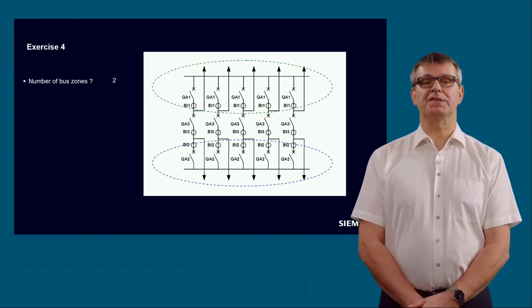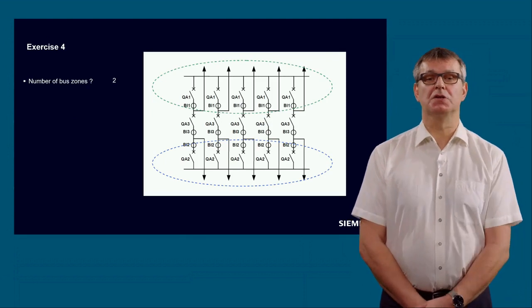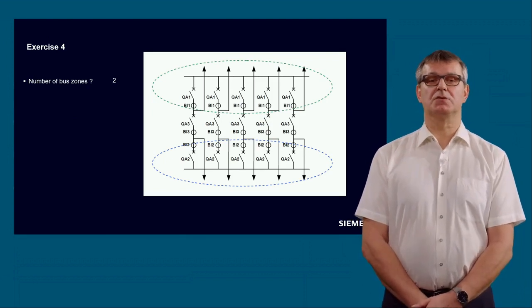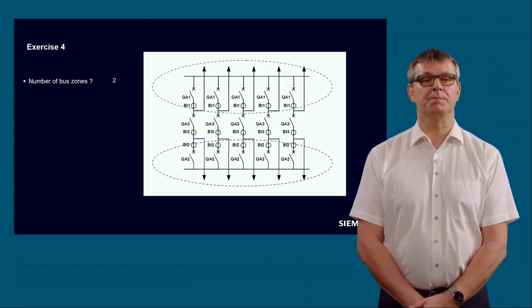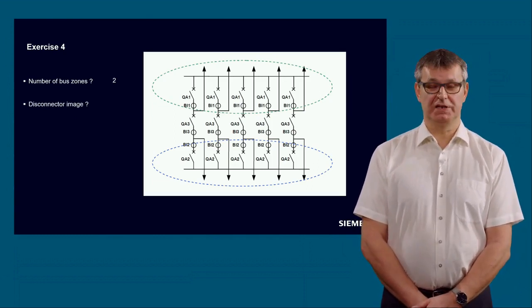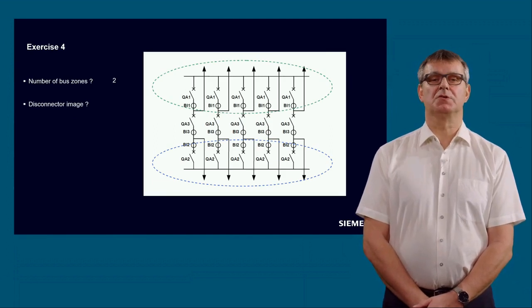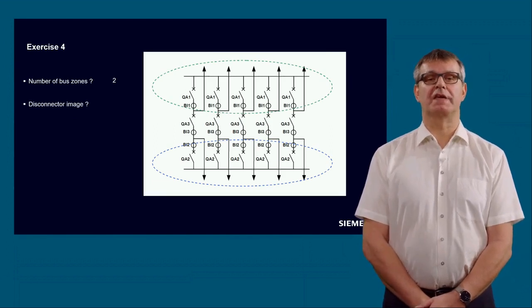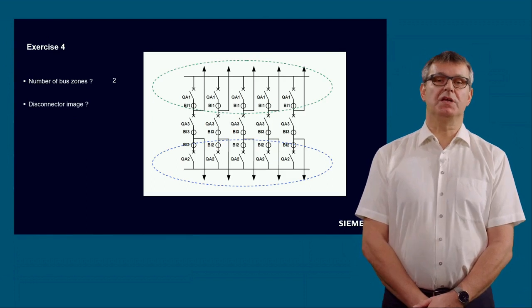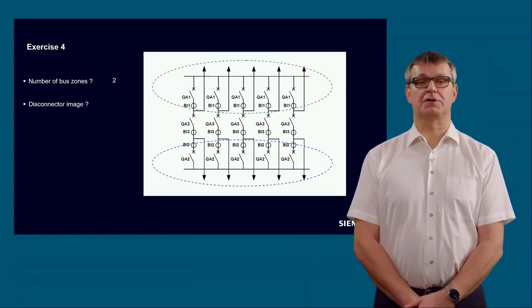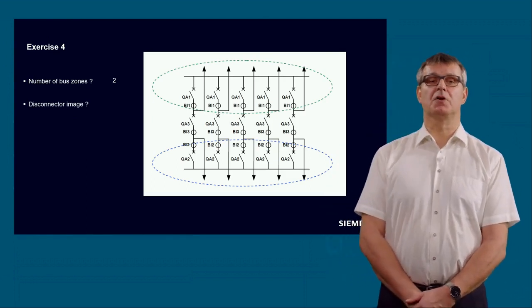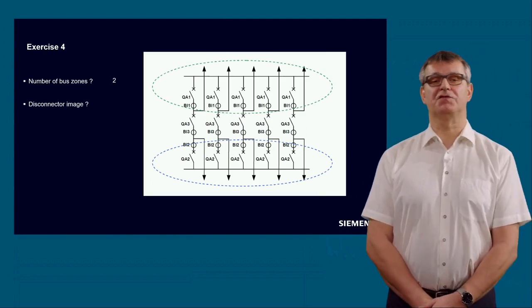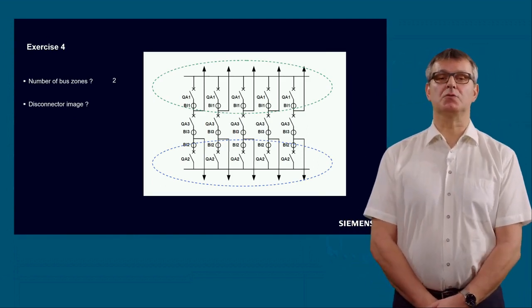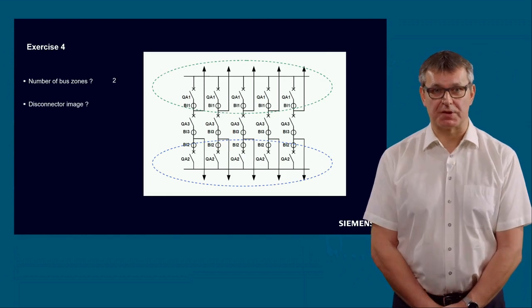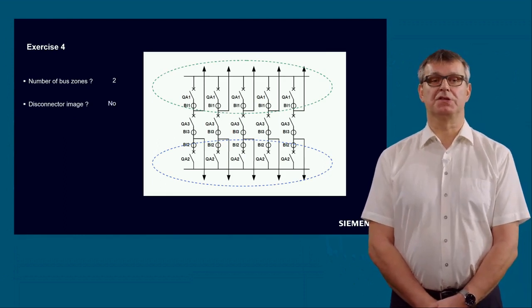And the number of bus zones, of course, is only 2. So you have 1 bus zone on the top and you have one bus zone on the bottom. Do we need a disconnector image? You have to look carefully. Here too, you can't assign any feeder current transformer to different bus zones. You can't assign this feeder current transformer either to the bus zone on the top or to the bus zone on the bottom. So we don't need a disconnector image.